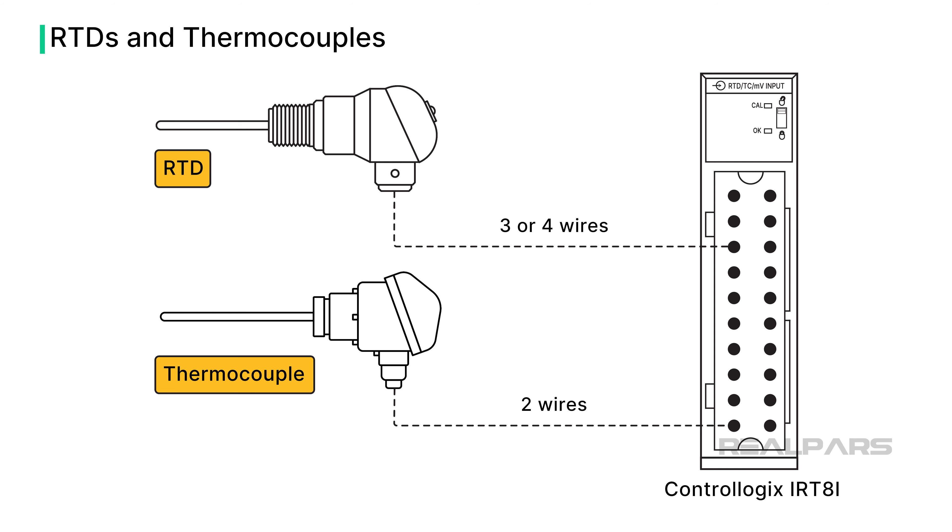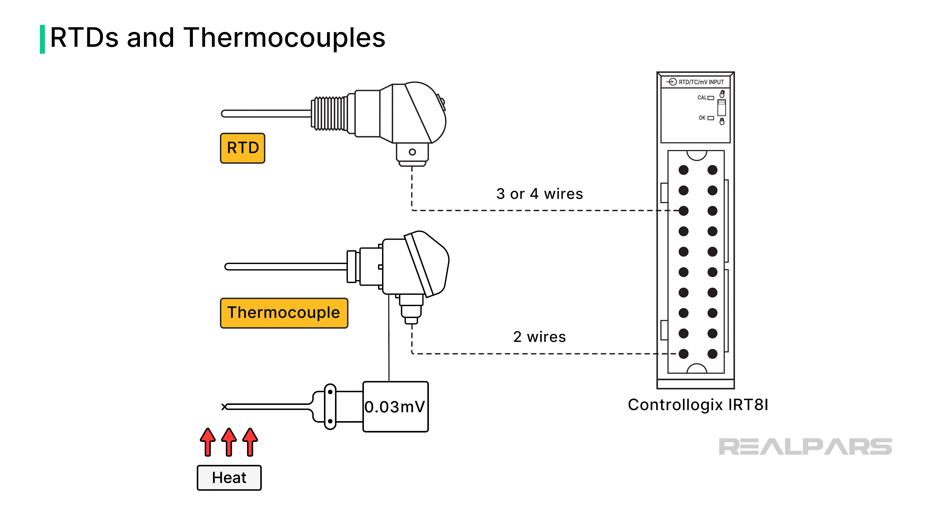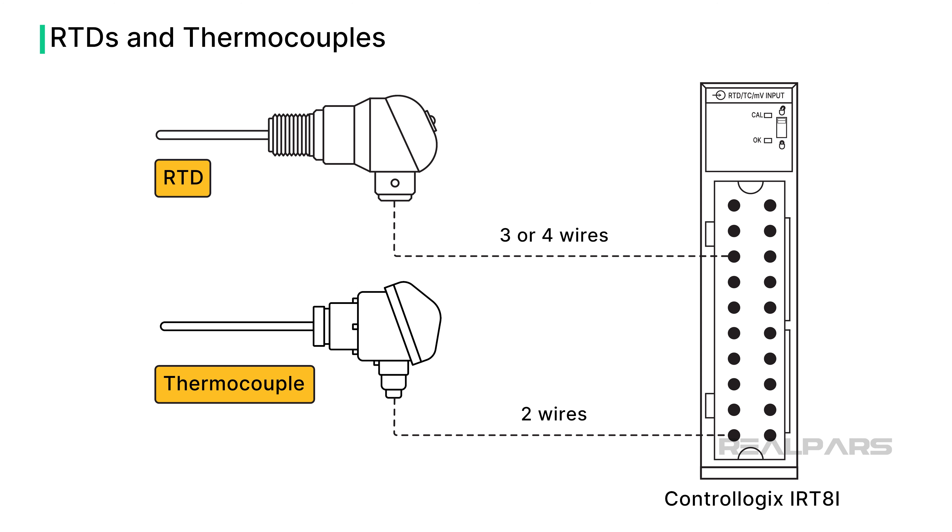This type of connection has pros and cons. The RTD changes resistance with a temperature change, and a thermocouple produces a change in voltage with a temperature change. Issues with wire length between the RTD and the module, and differing temperatures between the thermocouple sensing location and the module, need attention.